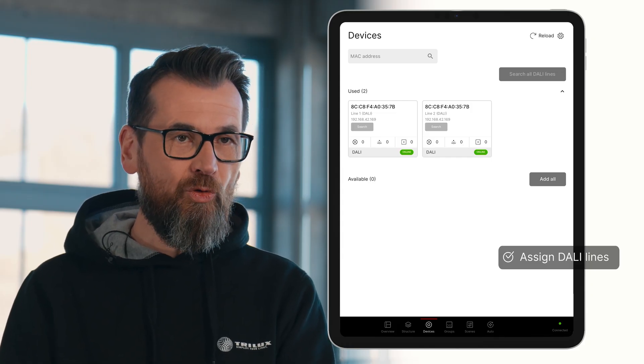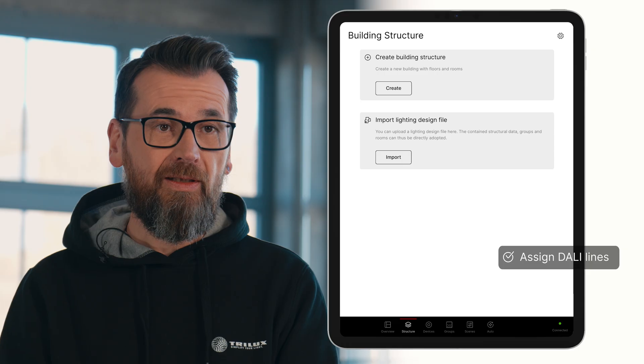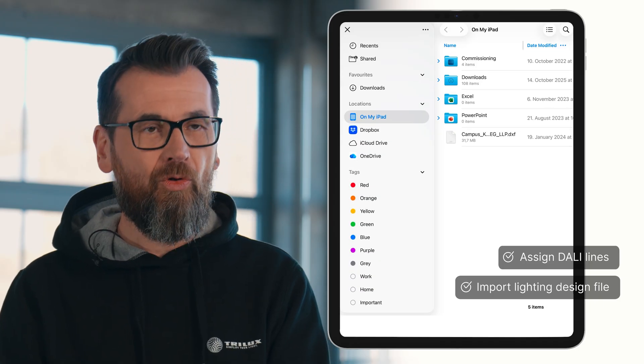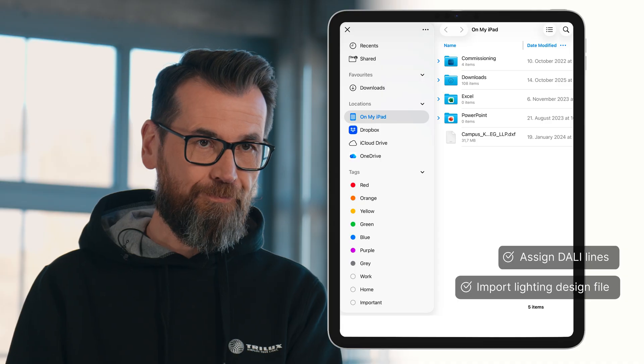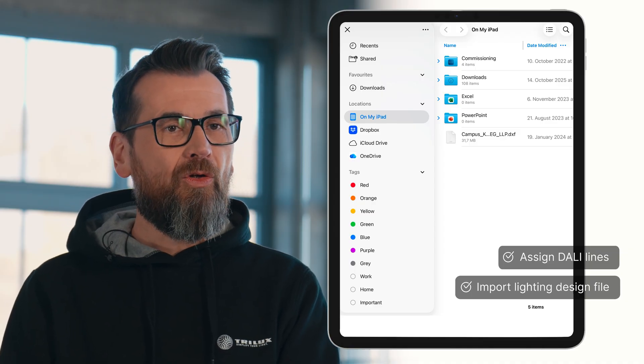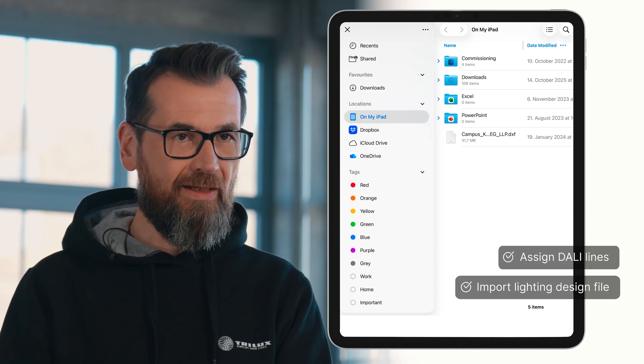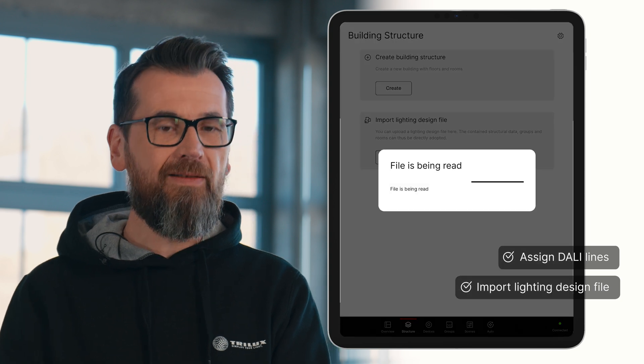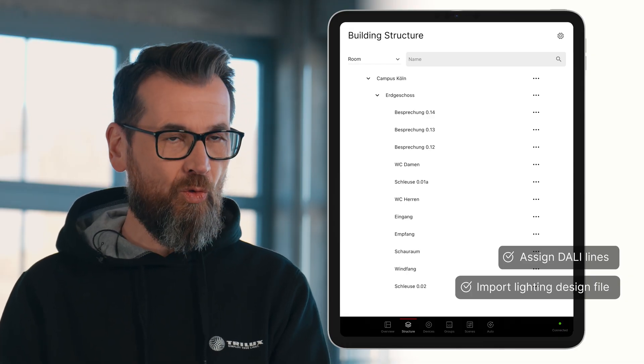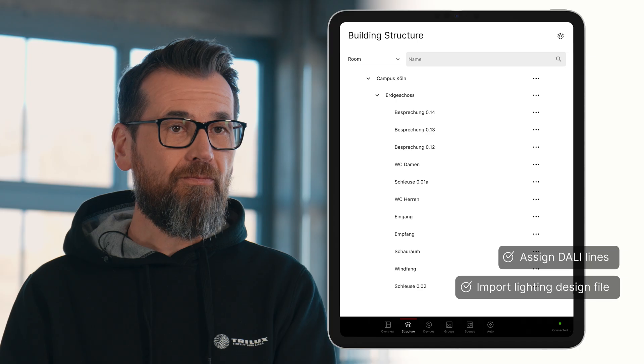Since this takes a little time, we'll meanwhile go to the Structure section to import a lighting plan. As Markus already mentioned, we select Import to import a DXF file from the tablet. Using the DXF file, for example based on a RELUX plan, we can directly import the building plan, the building structure, as well as all positions of the luminaires, sensors, and push buttons. I simply select the file, it is checked, and I can import it into the system. First, we see the building structure. This structure can be modified as needed by adding floors, rooms, or importing additional lighting plans — for example, more floors or even additional buildings.